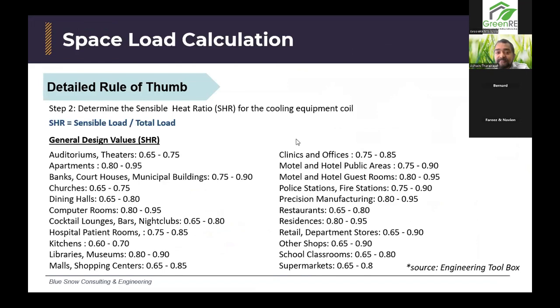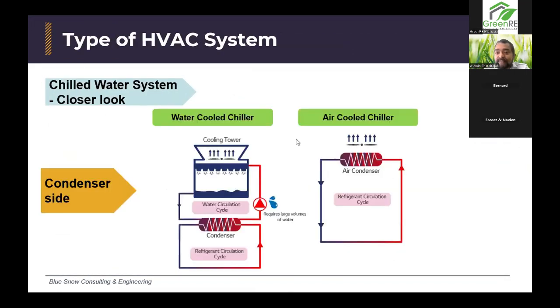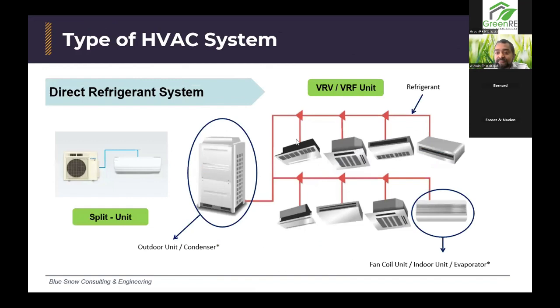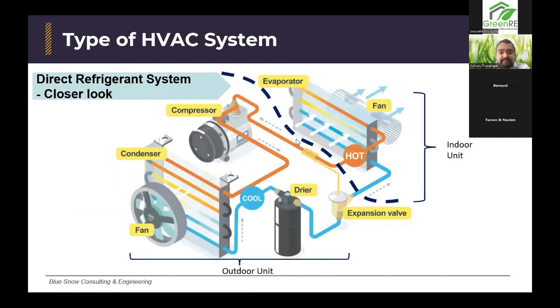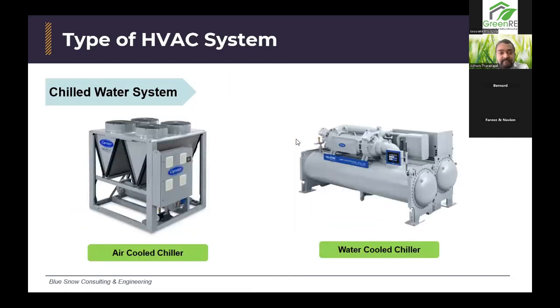Okay, I know where he's coming from because people often hear the word centralized, right? It's a common term here in Malaysia. Oh, central system. It can mean many things. It can mean the VRF. Oftentimes, it's the VRF versus the chilled water systems, meaning that all of the indoor systems are connected to a central outdoor system. So that is why the term central cooling comes in. So it can actually even be both. Sometimes you say, oh, I'm using a central system, but you go and check it. Really, it could be a VRF system. It's basically meaning all your indoor systems are connected to a centralized outdoor system.